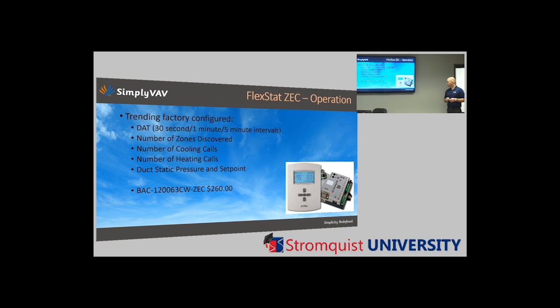And I think between the price of the zone equipment controller and the Simply VAV, we're really trying to sell pressure independent retrofits of VVT systems. And I think retrofitting a VVT is relatively expensive and you still get pretty poor performance because you're still pressure dependent. We're advocates for pressure independence because you can deliver to the zone true demand, true cooling and heating that they need.